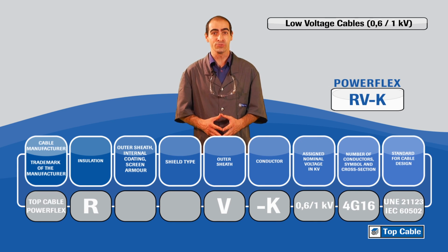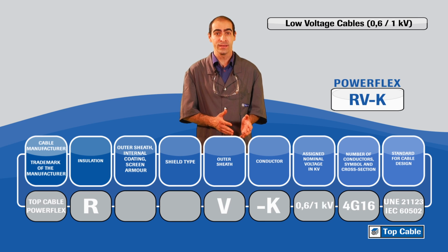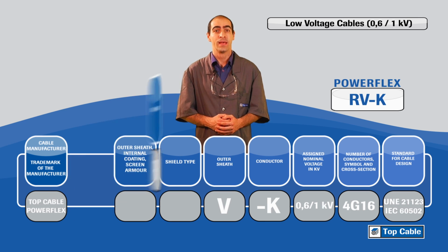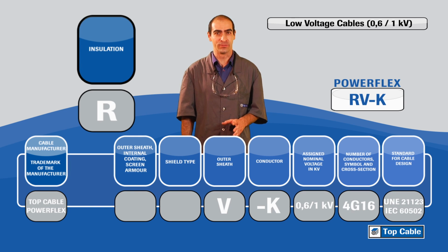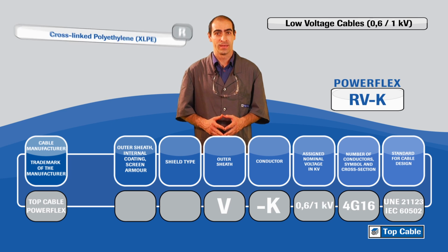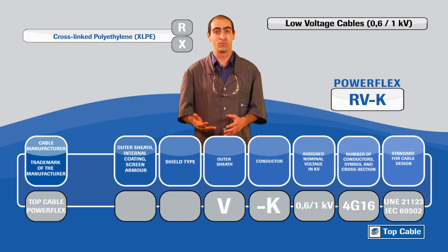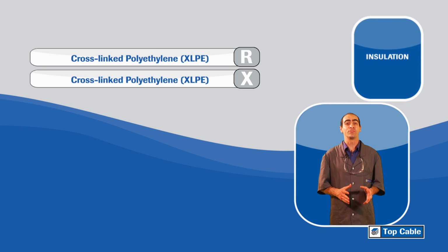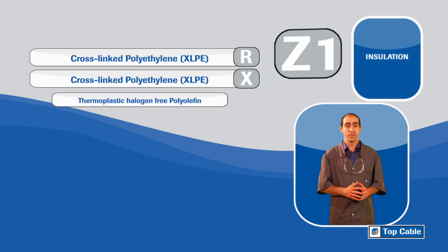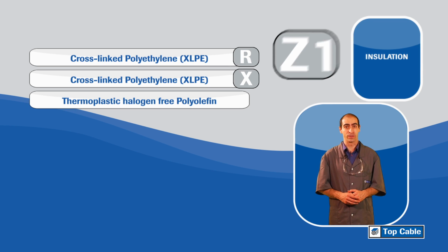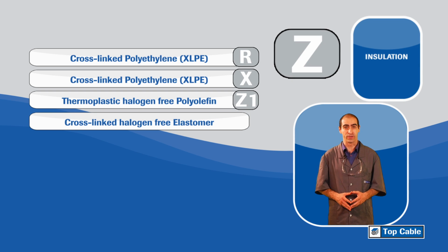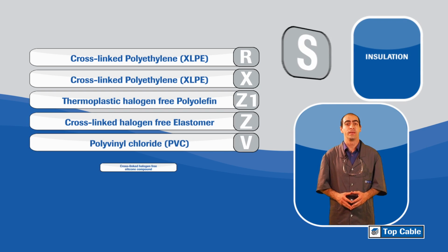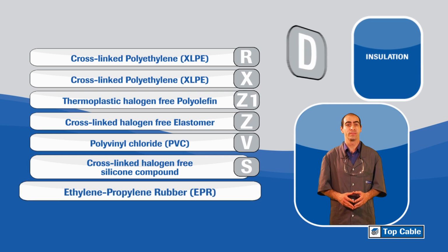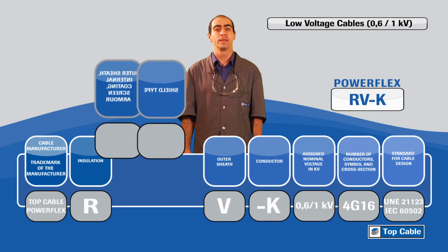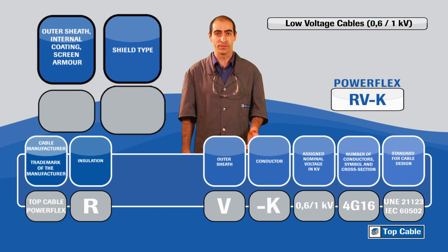nominal voltage, to the cable insulations, to metallic coverings, to the type of conductors, and to the final composition of the cable. R refers to the cable insulation. In this case, it is an XLPE cable. R, cross-linked polyethylene, XLPE, X. Other common insulation types are Z1, thermoplastic halogen-free polyolefin, Z, cross-linked halogen-free elastomer, V, polyvinyl chloride, PVC, S, cross-linked halogen-free silicone compound, D, ethylene propylene rubber, EPR. If there is no internal covering or any screen armor, no letter is used.